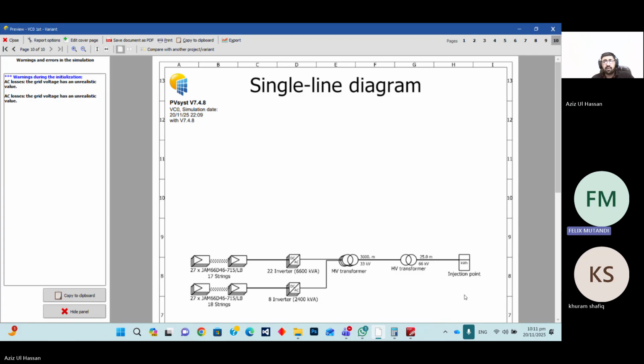Yes, but I need to understand well what injection points are. Let's talk about the MV transformer and the HV transformer. I think those two pieces of equipment must be around your utility plant. So the injection point for the MV transformer is the switchgear between the MV and HV transformer, and I must put the cable length between the MV transformer and the switchgear there. Yes, you are right. This injection point is 3,000 meters, the injection point between the transformer and the HV transformer.